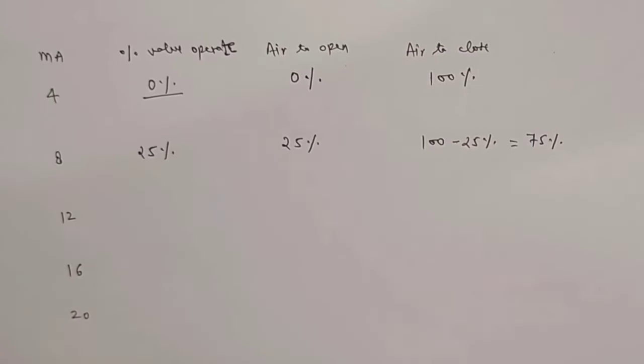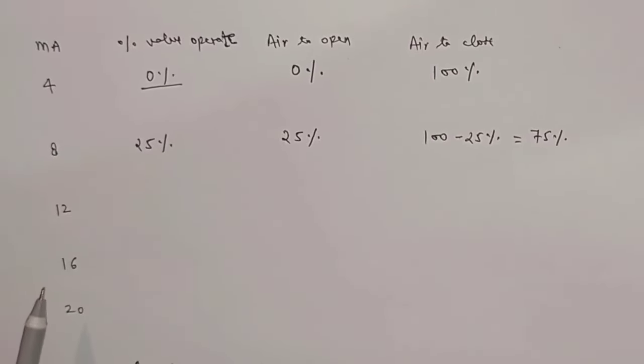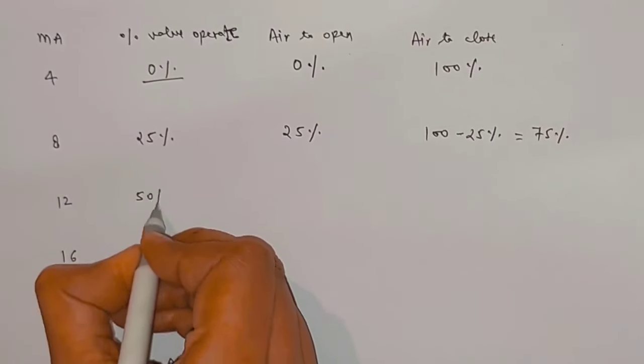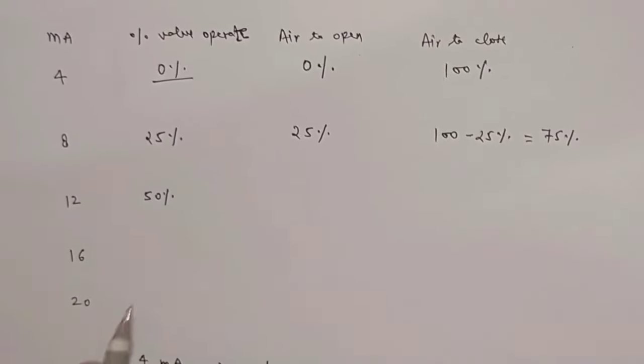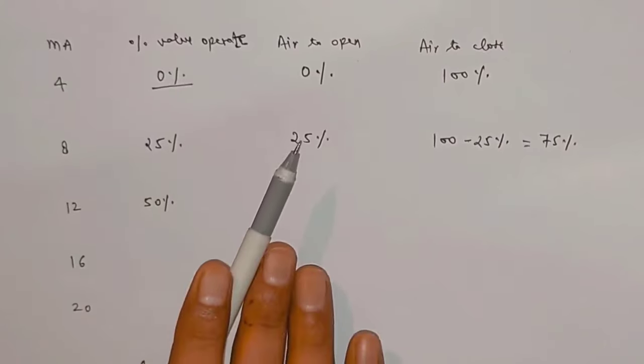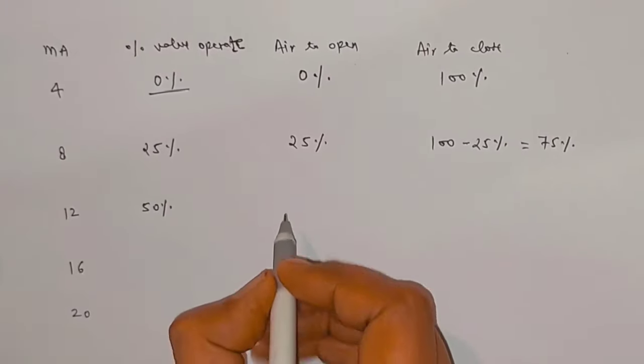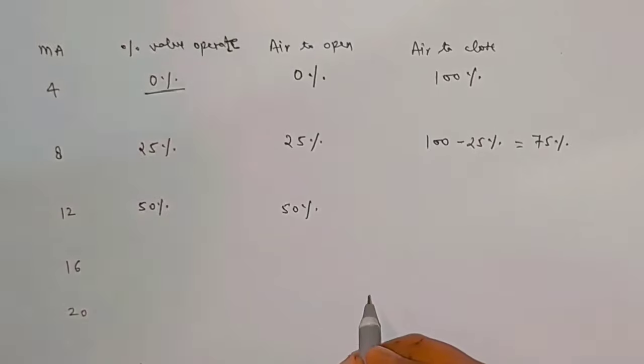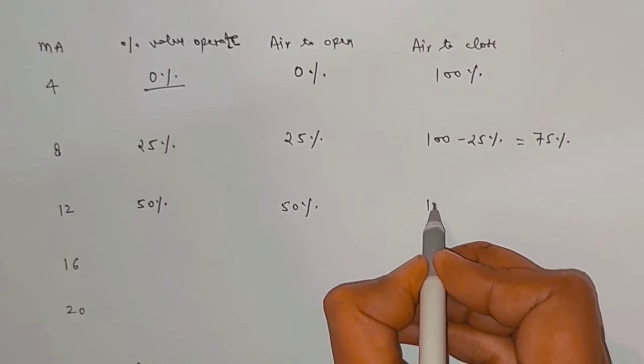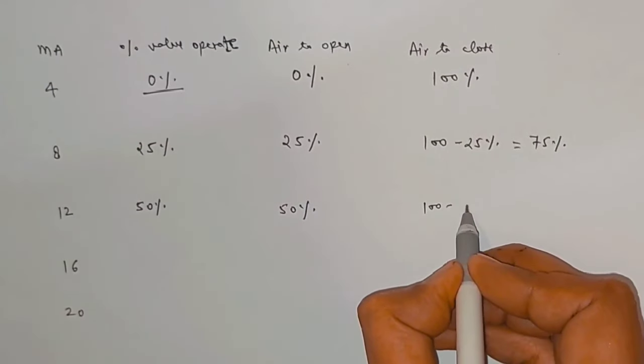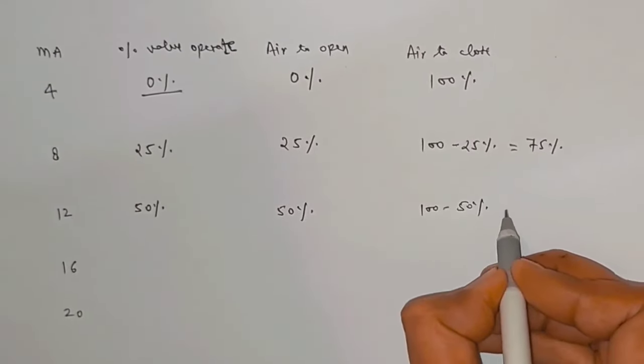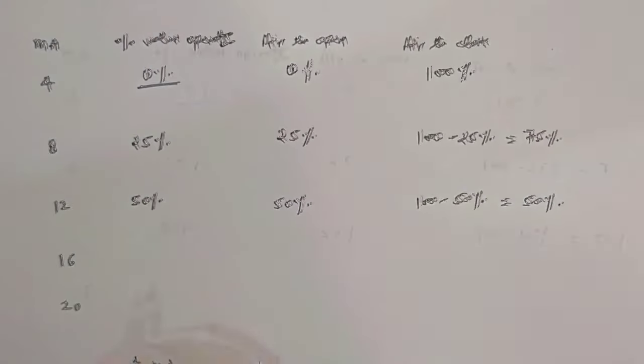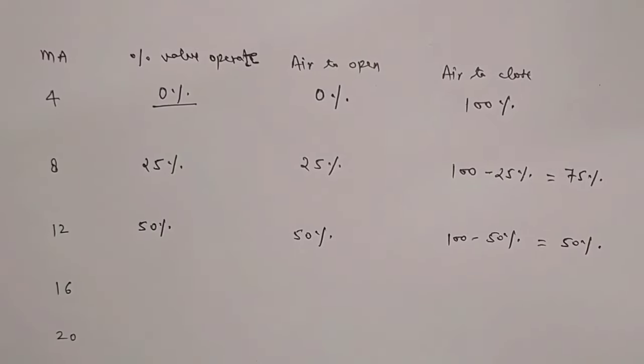At 12 milliampere signal, it will be 50%. So the opening percentage of the air-to-open control valve is 50%. And the opening of the air-to-close control valve will be 100 minus 50%, so it will become 50%.